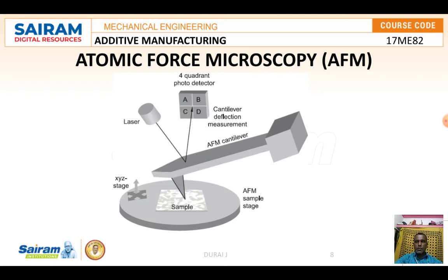Atomic forces are used to map the tip-sample interaction, so it is often referred to as a scanning probe microscope. There are atomic force microscope techniques for almost every measurable force interaction, like van der Waals, electrical, magnetic, and thermal. For some more specialized techniques, the tips are modified and software adjustments are needed.